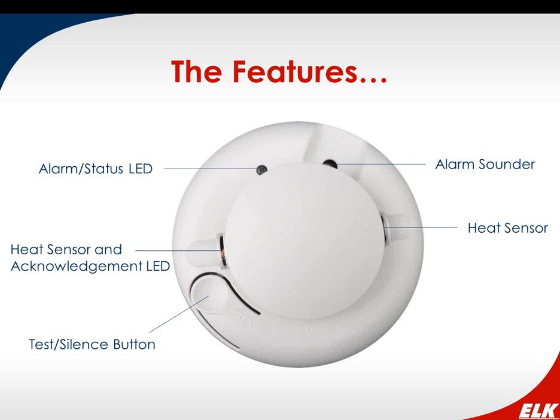With the test silence button, if you have an alarm condition, if it senses smoke or heat and you press that to silence it, it's going to silence it for several seconds, but if there's still smoke in the chamber, it's going to continue to sound. So that's something to be aware of. That's by design the way that it works, because if it's still sensing smoke, you certainly would want to be aware of that.